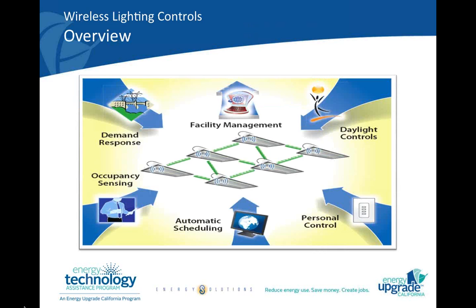So on the screen, there's an illustration that shows the basic components of how a wireless lighting control system works. Basically, each fixture is equipped with its own lighting controller, which sits in the ballast cavity itself, and is about the same size as a ballast, about the same size as a stick of butter, actually. These controllers then communicate with all the fixtures surrounding it, which creates a mesh network that operates on Zigbee protocol, if anybody's familiar with wireless networks at all. So if for some reason one fixture goes offline, it doesn't interrupt the network, and the signal just jumps around it.